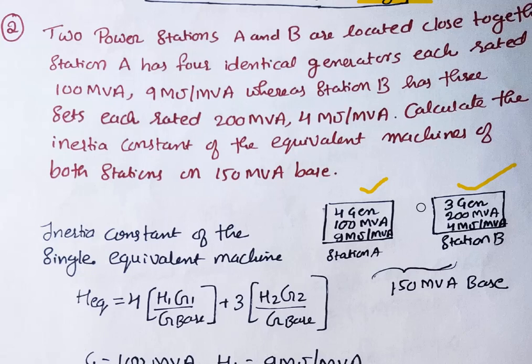Since the stations are located close together, the generators of both stations can be treated as a single equivalent large machine. The equivalent inertia constant is: H_eq = (4 generators × H1 × G1 / G_base) + (3 generators × H2 × G2 / G_base), where G_base = 150 MVA, G1 = 100 MVA, H1 = 9, G2 = 200 MVA, H2 = 4.